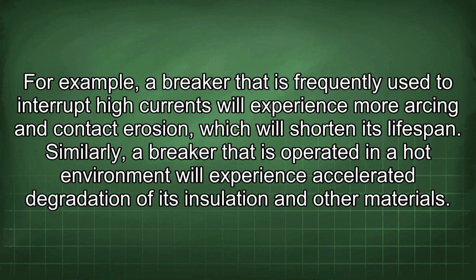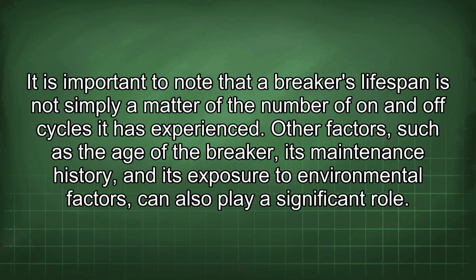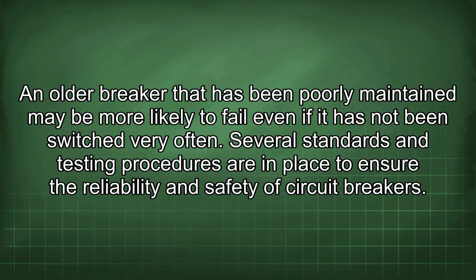insulation and other materials. It is important to note that a breaker's lifespan is not simply a matter of the number of on and off cycles it has experienced. Other factors, such as the age of the breaker, its maintenance history, and its exposure to environmental factors, can also play a significant role. An older breaker that has been poorly maintained may be more likely to fail even if it has not been switched very often.